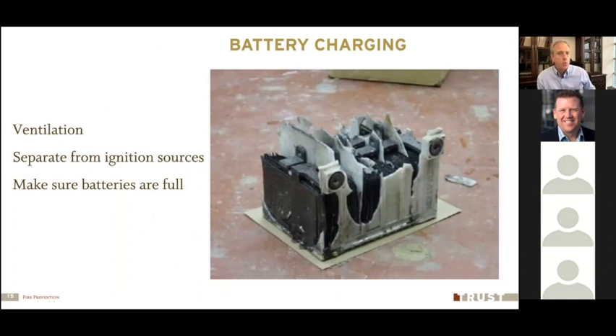If you have old wet cell batteries that you're charging, it's very important to make sure that those cells are full, and that in the areas where you charge those batteries, you've got good ventilation. You may need to bring in extra ventilation in that area. A wet cell battery, when it's charging, produces hydrogen gas and can cause these batteries to explode, or even if that gas is leaking off into a closed area, say a room where you're charging those batteries, it could present a significant explosion or fire hazard in that room as well.